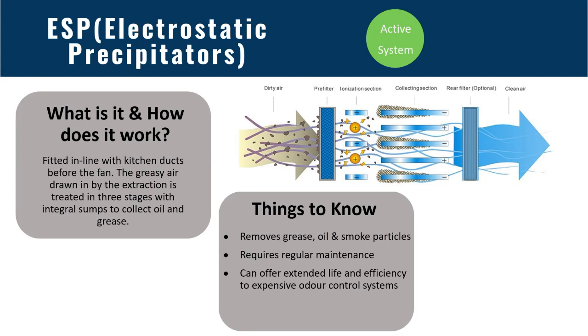Things to know about this system: it removes grease and smoke. They're considered to be energy efficient, and a single pass ESP can achieve a grease and smoke removal efficiency of 95 to 98%, depending on the manufacturer. The system does require regular maintenance to keep it effective and efficient, and the capital investment is high.